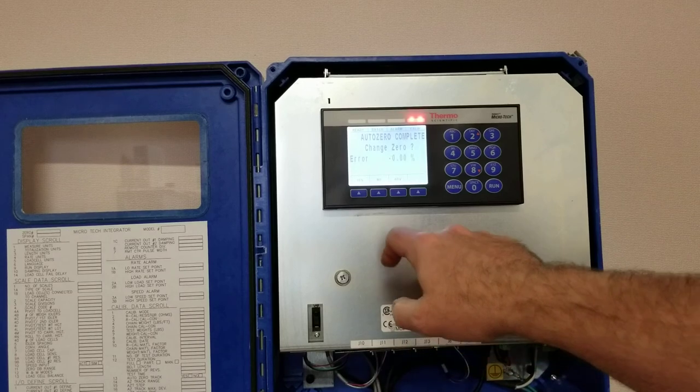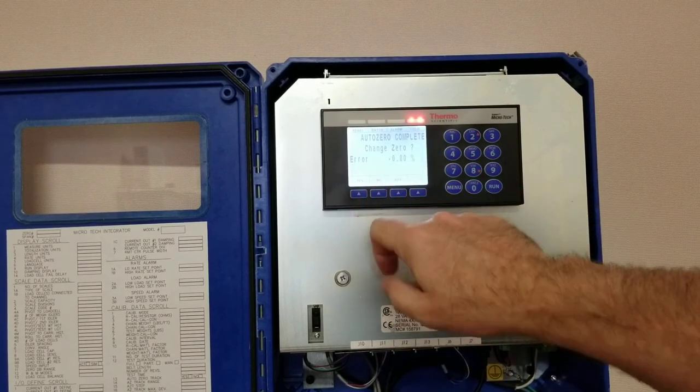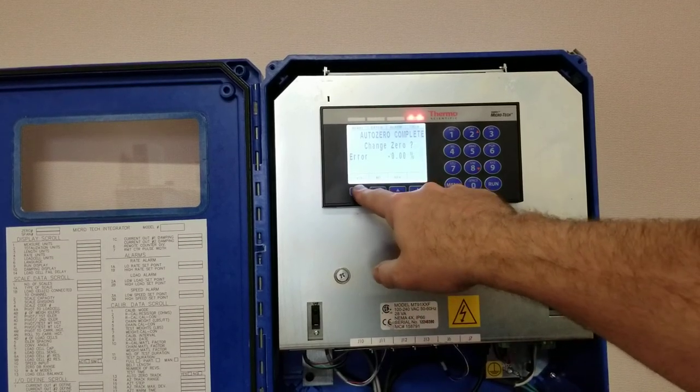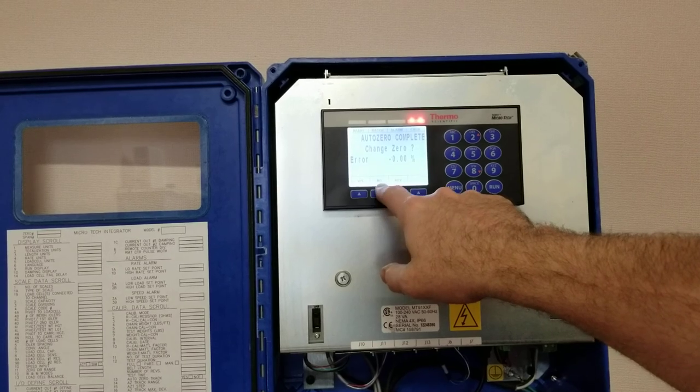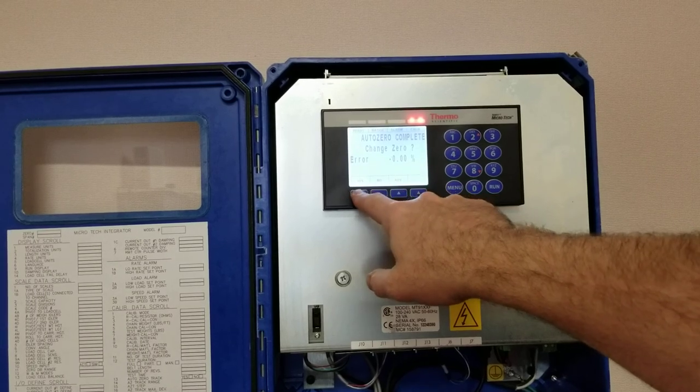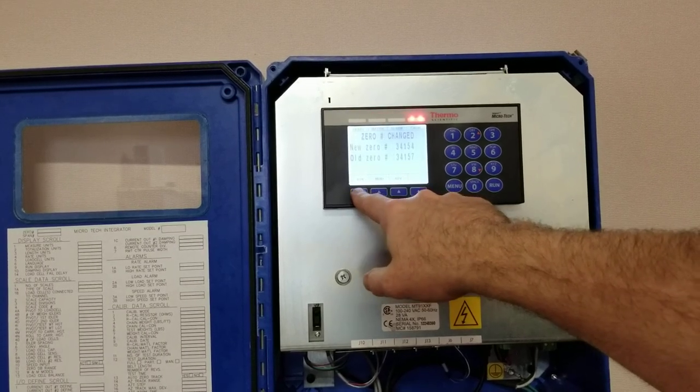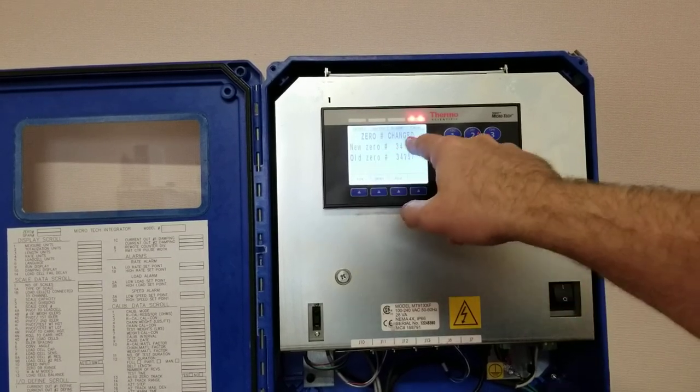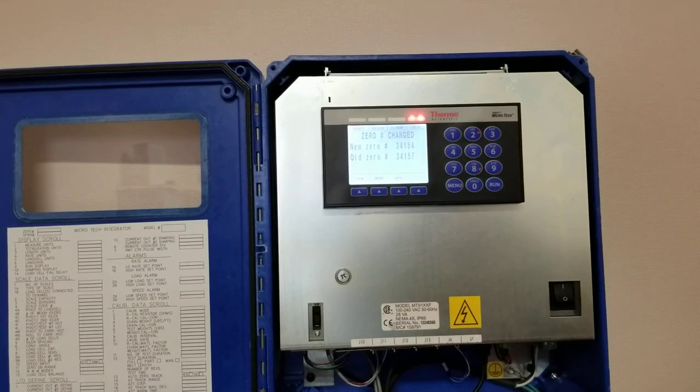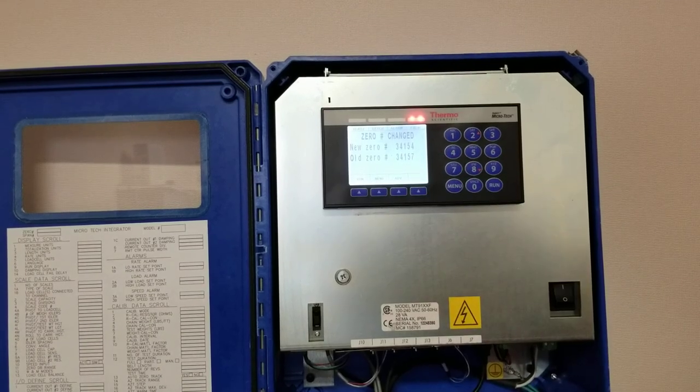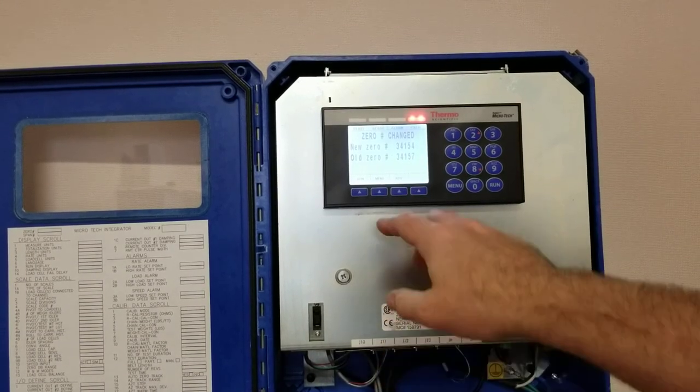All right, so in this case my error is close to zero, so I can either say no to accepting it or press yes. I'll just press yes in this case, and what it does is it establishes a new A to D value for zero.